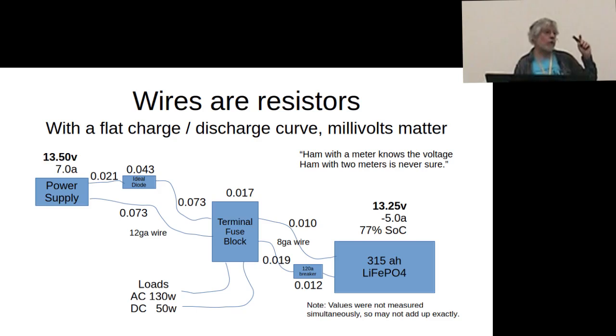14 gauge is good for 15 amps. Anyway, I've got 12 gauge wire going from the power supply down to the terminal block, and I think 8 gauge going to the battery. I'm pulling 7 amps out of the power supply—the sun had just gone down, so the power supply kicks in with 7 amps. The battery's feeding out 5, for a total of 180 watts going into the load, which is running a computer monitor and that kind of stuff.